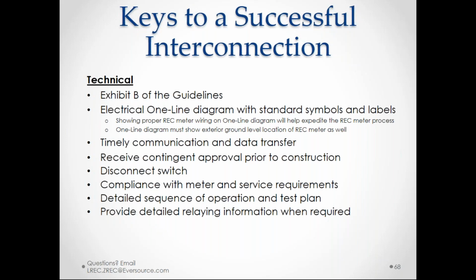Other keys to success: please pay attention to Exhibit B of the guidelines. Those are the technical requirements for all projects that fall in the fast track process. So that's where you'll see requirements such as needing a redundant relay for projects over 1 megawatt, and where you can see more specific technical information such as settings requirements for inverters, and just in general the IEEE and other technical standards that must be followed. Another key, obviously, in your one line, please make sure that you're labeling things correctly, that you're identifying clearly the number, model, and size of inverters that you're proposing. We're less concerned with panels, but certainly those should be shown.